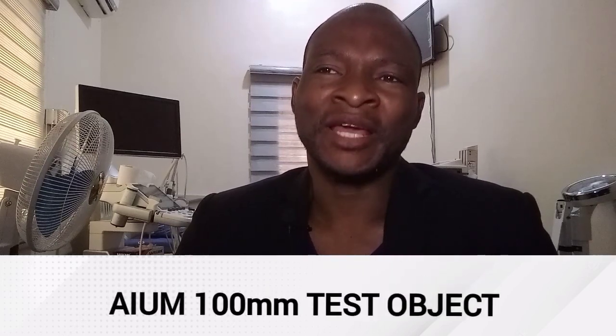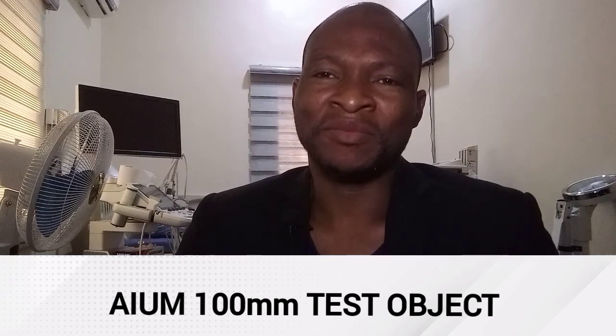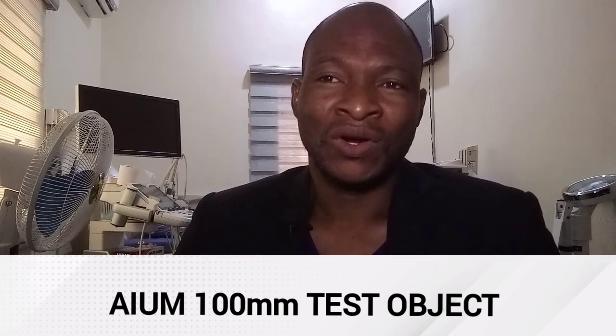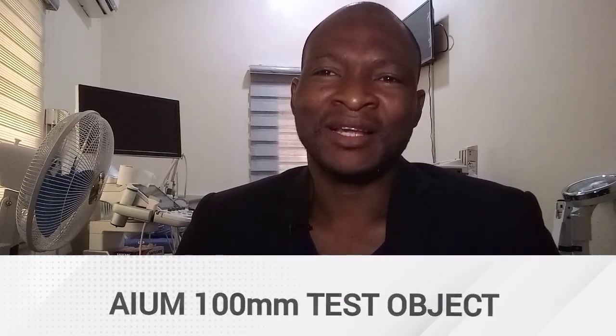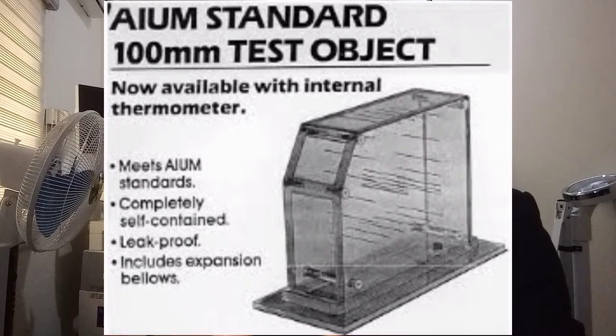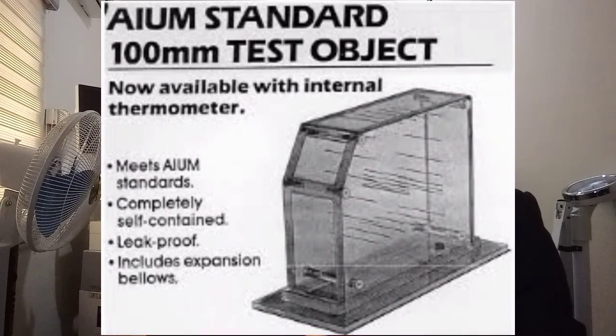Now, the AIUM 100 mm test object has been developed by the American Institute for Ultrasound in Medicine. It is a plexiglass box of fluid with stainless steel rods fixed within it. Now, the fluid is degassed. The fluid is degassed water that is mixed with algicide, that is algae inhibitor, and 9% alcohol at 22 degrees centigrade or room temperature to bring its propagation speed to 1,540 meters per second, which is the velocity of sound through soft tissue, which the equipment calibration is also based on.